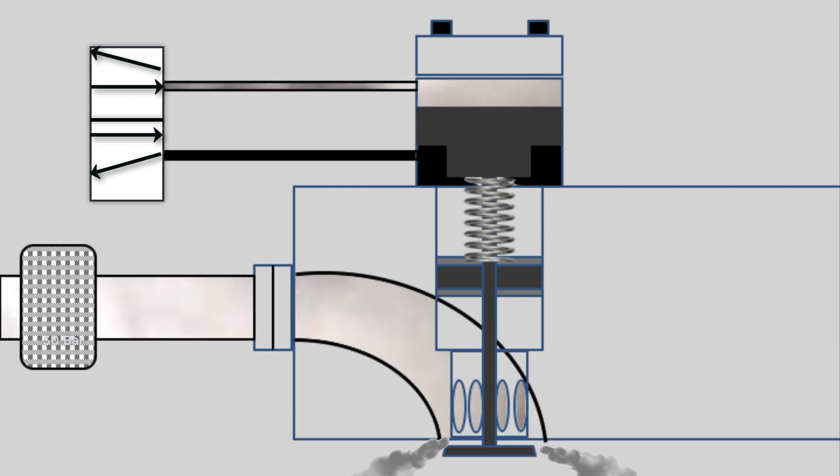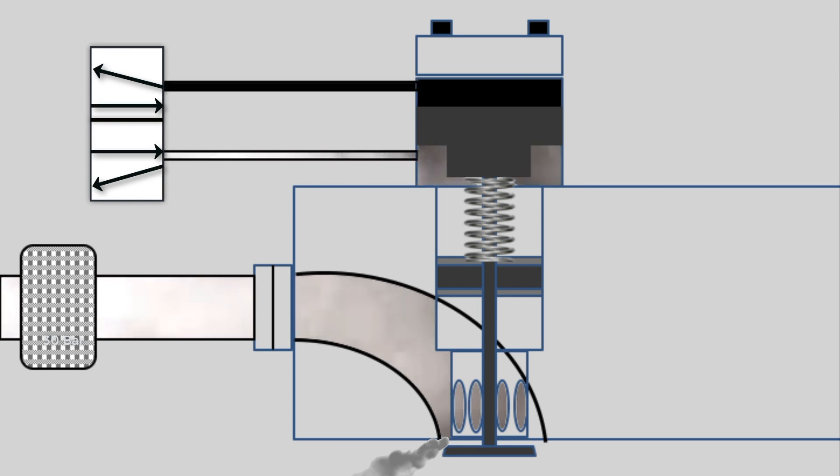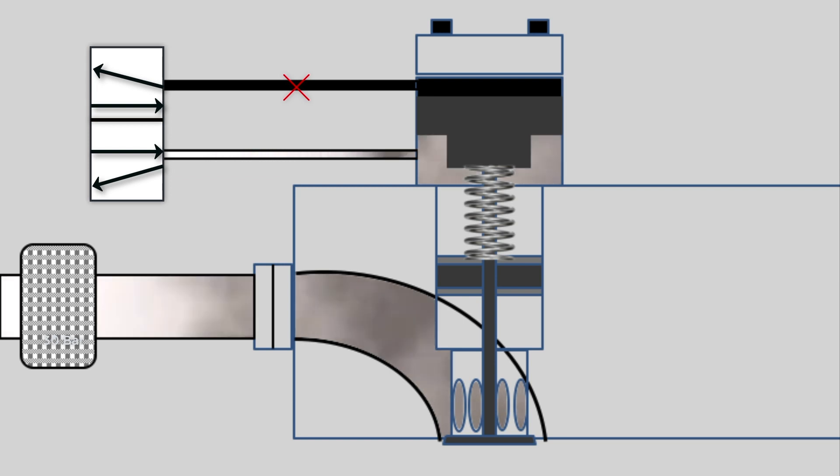To close the valve, the air is supplied to the bottom part, venting the upper portion of the operating piston. This also helps in providing a cushioning effect to the valve as the air on top dampens the closing.